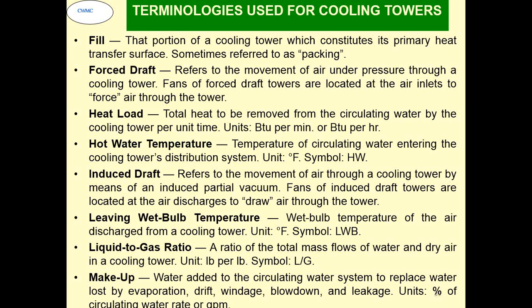Heat load, total heat to be removed from the circulating water by the cooling tower per unit time. Units are BTU per minute or BTU per hour. Hot water temperature is the temperature of the circulating water entering the cooling tower distribution system. Units are again degree Fahrenheit or degree centigrade. Induced draft refers to the movement of air through a cooling tower by means of an induced partial vacuum. Fans of induced draft towers are located at the air discharges to draw air through the tower. Leaving wet bulb temperature. Wet bulb temperature of the air discharged from the cooling tower. Units are again degree Fahrenheit or centigrade.